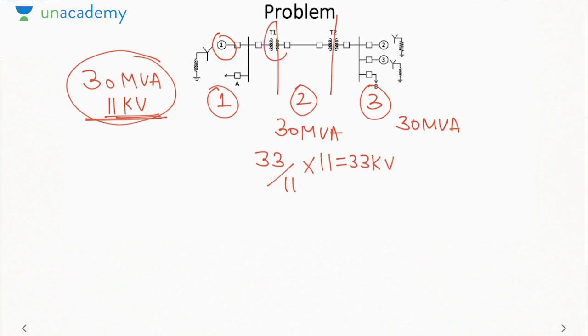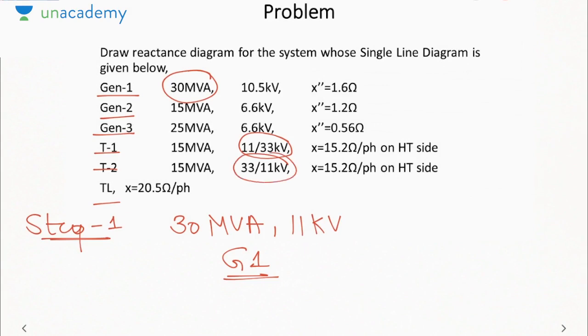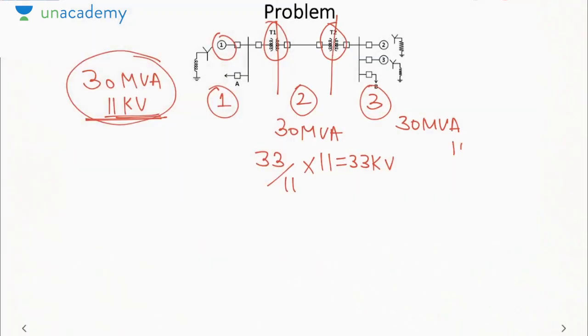Now the secondary voltage of T1 becomes the primary voltage of T2. The rating of T2 is 33 by 11, so the T2 secondary voltage will be 11 by 33 into the primary. The primary voltage is 33, so it will be 11 kV. So now I have got the base for all the 3 sections: 30 MVA 11 kV, 30 MVA 33 kV, 30 MVA 11 kV. Now the next step is to calculate the per unit impedances on the bases in the different sections. So let me start with generator G1.